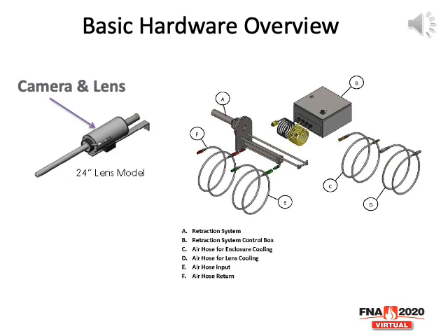Item A shown there is the main retraction system that we just spoke about. This is what the camera mounts to and slides in and out of the furnace, and that gets mounted to the furnace. And then the other items around that are just the cooling facilities and the controls that monitor all the air pressures or water pressures and so forth. So those all work in concert together to ensure that everything is operating and getting the proper cooling, and it's safe and reliable. With all this together, it's all mature. These have enabled infrared cameras to run for many, many years at very high temperatures with very reliable performance and accurate measurement for process control.